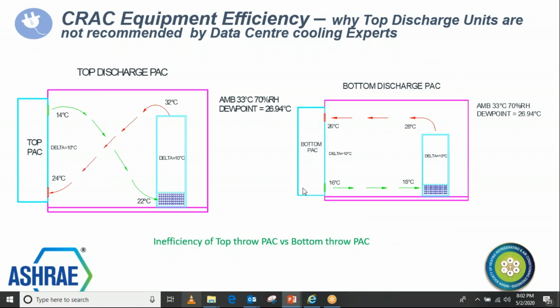Imagine another scenario where you have a cooling unit discharging cold air from the bottom. This is just a front example, and it is sucking here, following the natural airflow pattern. Imagine you have a false floor, a raised floor. The cold air goes under the raised floor to the equipment, exchanges the heat and comes back from the rear side or from the top side, and this cycle is continuous. So it is very important to understand that in many applications, although the equipment has provision for bottom front suction or bottom suction, the air conditioning system still uses a ducted type.